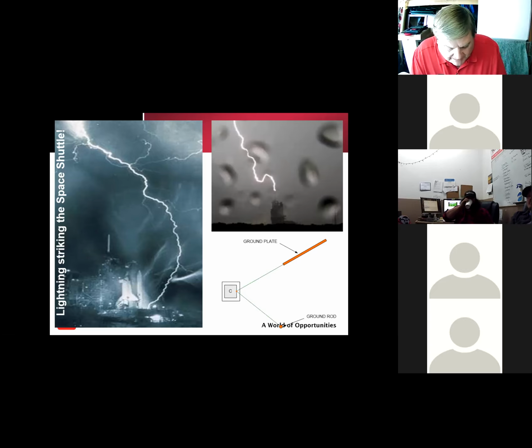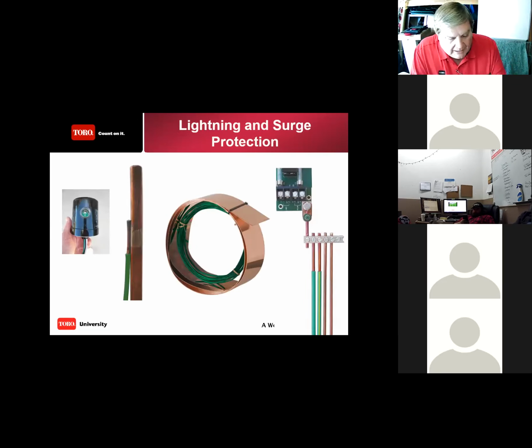Making certain your dissipation is away from anything that'll be picked up, so that the sphere of influence isn't in contact with that 2-wire path. That's the walk away. Whether you use a ground rod or a ground plate, that's just a ground plate coiled up. Over here on the left, that is a surge device that you put at the controller. Probably one of the higher end quality surge protectors. You've got a little screen here, which gives you a green light when it's working. And if the green light's not on, it's not necessarily properly grounded and probably not working. So good devices to have.